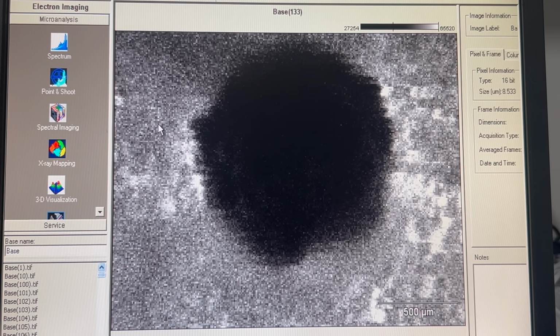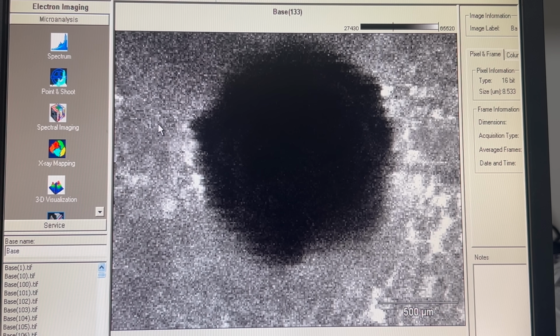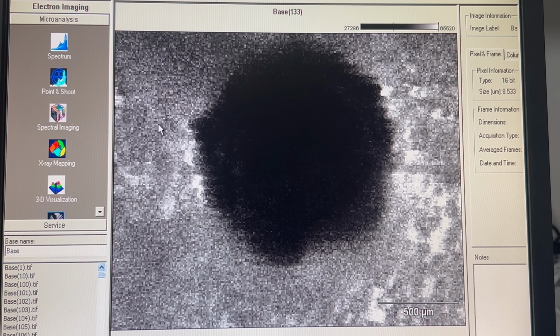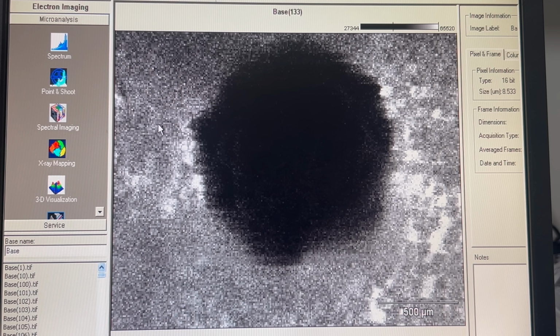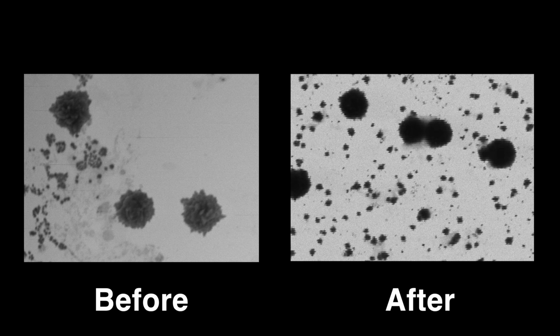Alright, that actually looks pretty good. The nanoparticles appear dark and two-dimensional, which means that this is definitely a transmission image and not a secondary electron image. The new shield is a very clear improvement when it comes to blocking unwanted secondary electrons.